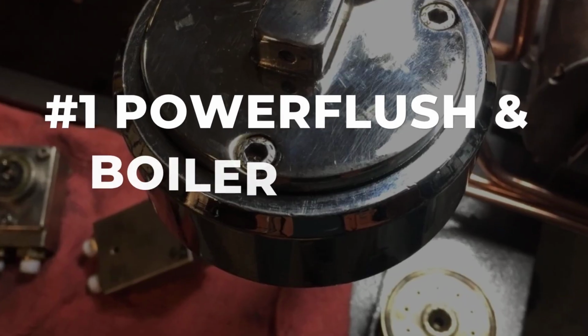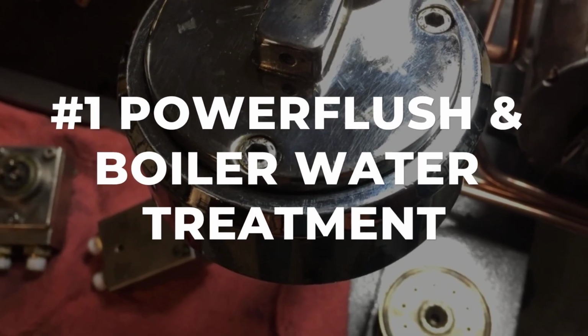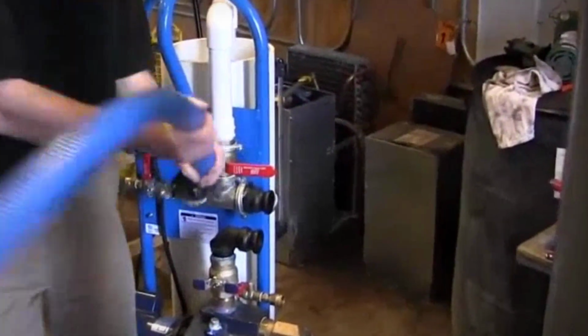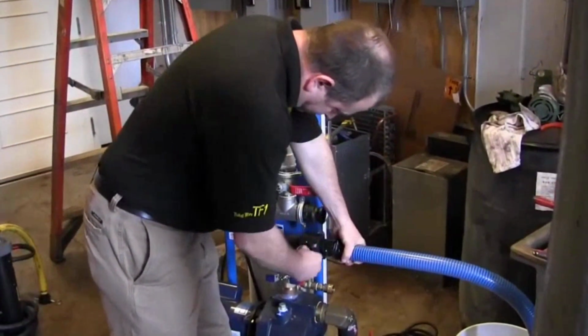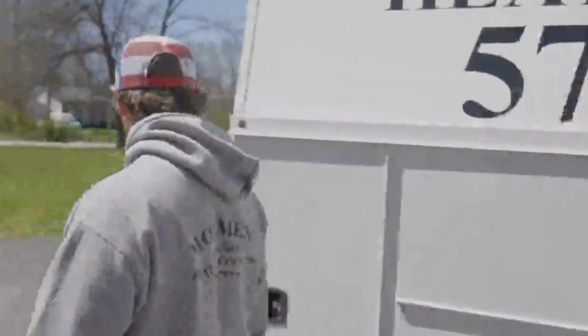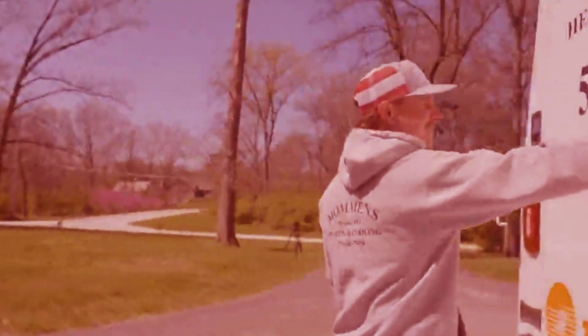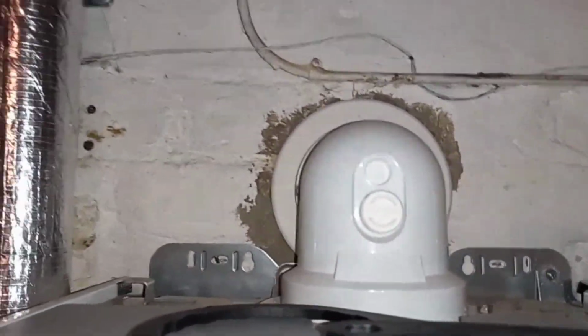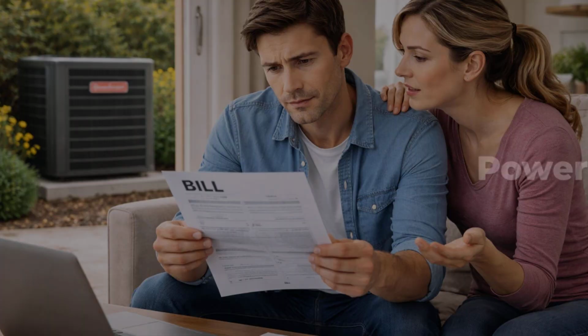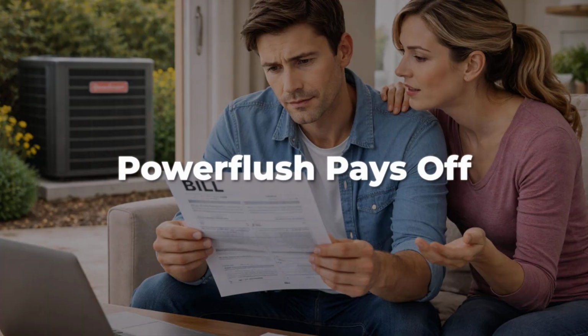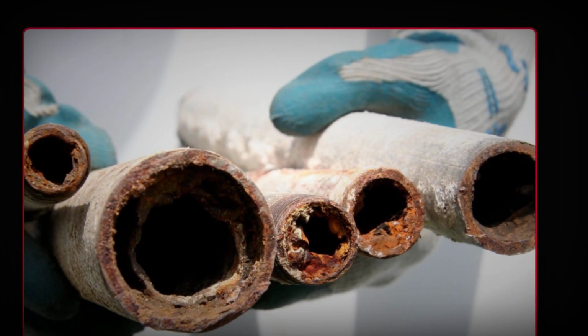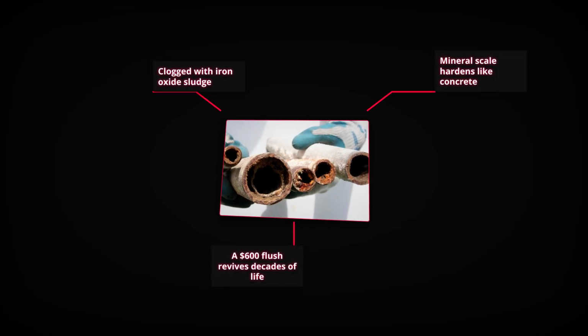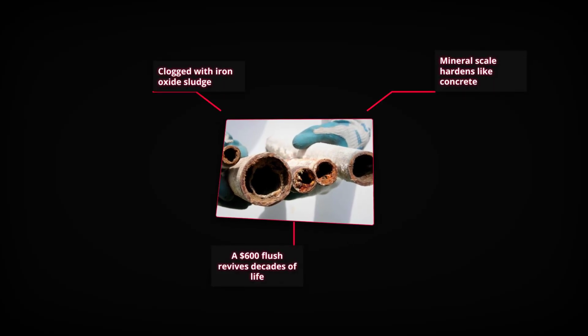And finally, in first place, nothing shatters the boiler replacement myth quite like a full power flush combined with chemical water treatment. This is the secret that HVAC companies guard the tightest, because it is the one move that can add a decade or two to your system's life for a fraction of the price of a new install. Inside every aging boiler, sludge builds up year after year, iron oxide from radiators, mineral scale from tap water, rust flakes from every threaded joint.